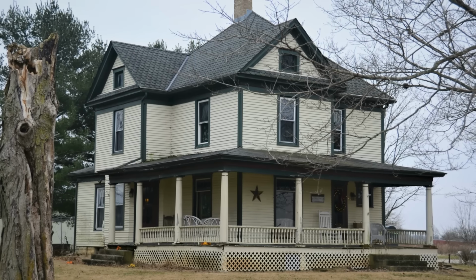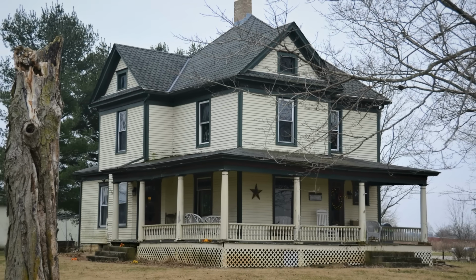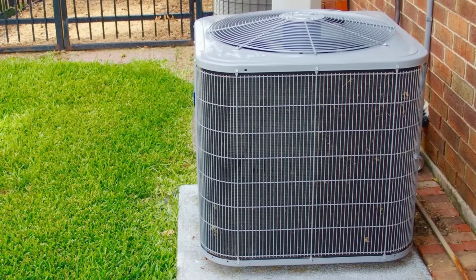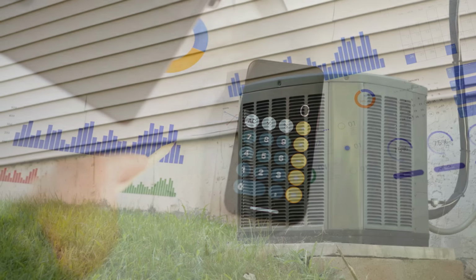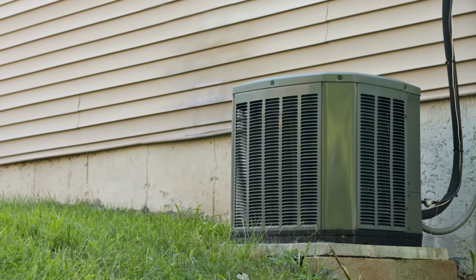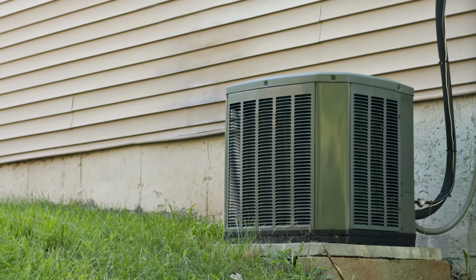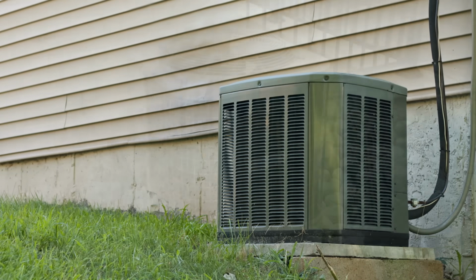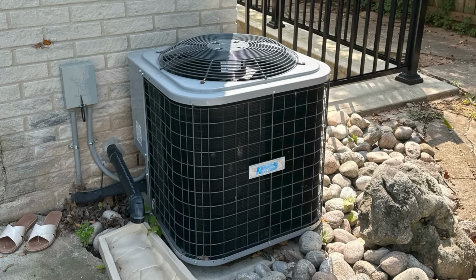Now, this wasn't a problem in uninsulated or poorly insulated buildings. The air conditioning system was running basically 24/7, and while the energy bills were expensive, the buildings received incidental dehumidification benefits because air conditioning systems are basically dehumidifiers. As long as the air conditioning is running, it's dehumidifying.